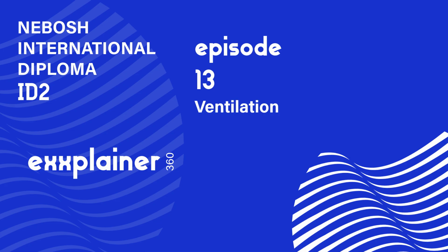Okay. And the third key measurement? Static pressure. This measures the pressure perpendicular to the airflow, again, using a manometer connected to a port in the ductwork. What does that tell you? It's often used to check the condition of the filter. Filters create resistance, a pressure drop. If the static pressure reading across the filter is much higher than it should be, it means the filter's clogged, blocked.